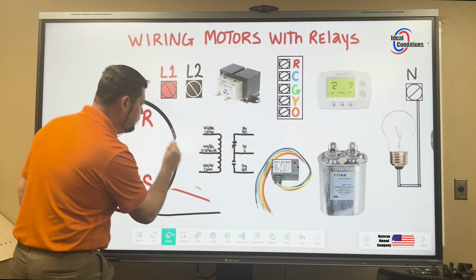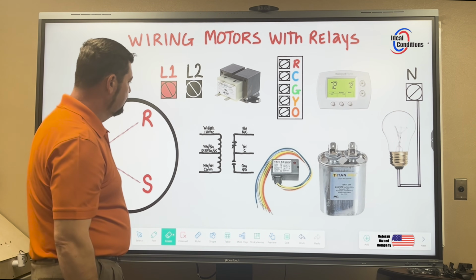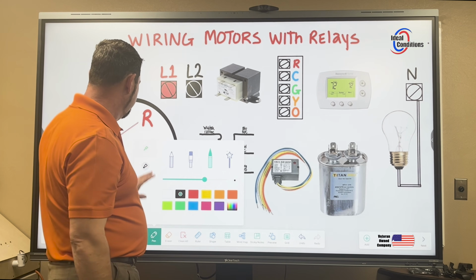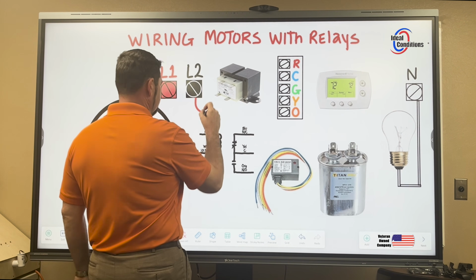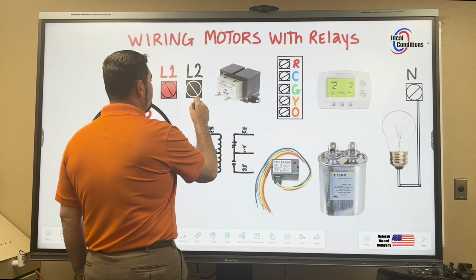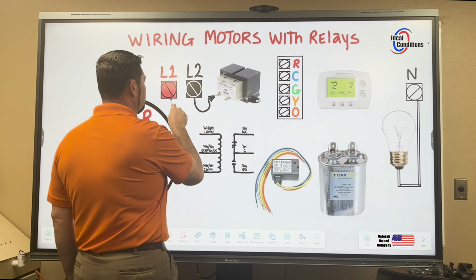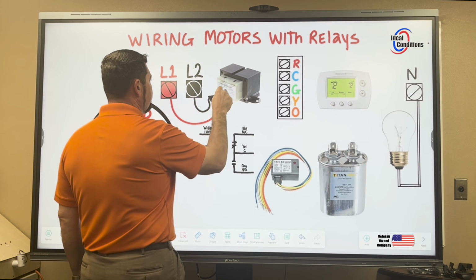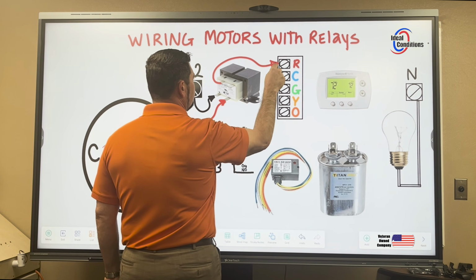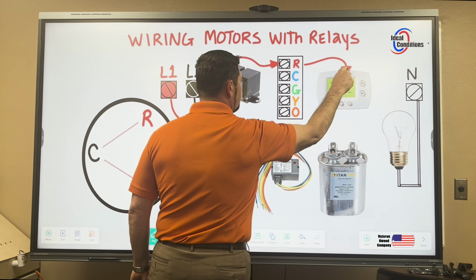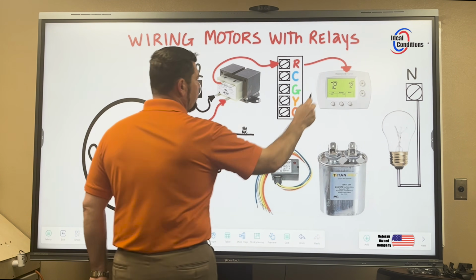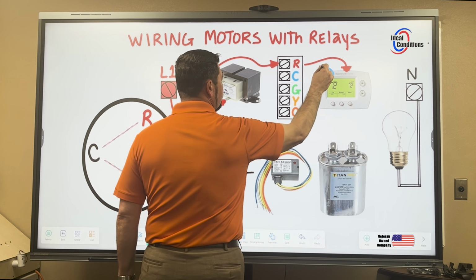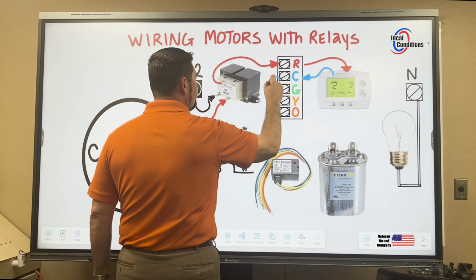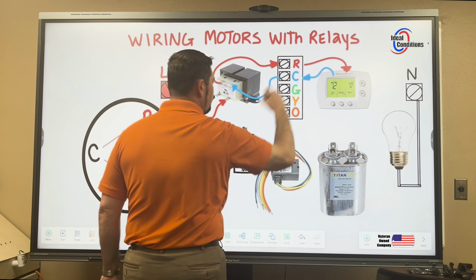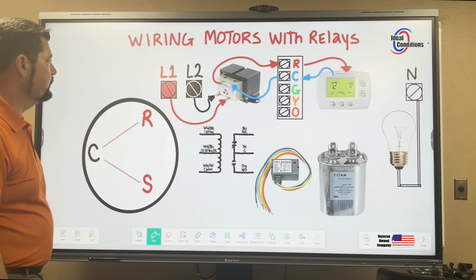Erase it because it's easy and we can always do it again, right? All right, so now it's a clean board. We're going to go ahead and work on 2 loads real quick. We're going to say we need 1 leg here, 1 leg here. That puts out 24 volts. Here comes to here. Path back to the low voltage terminal block and then back to common, creates the loop. And now we have a display on the thermostat.